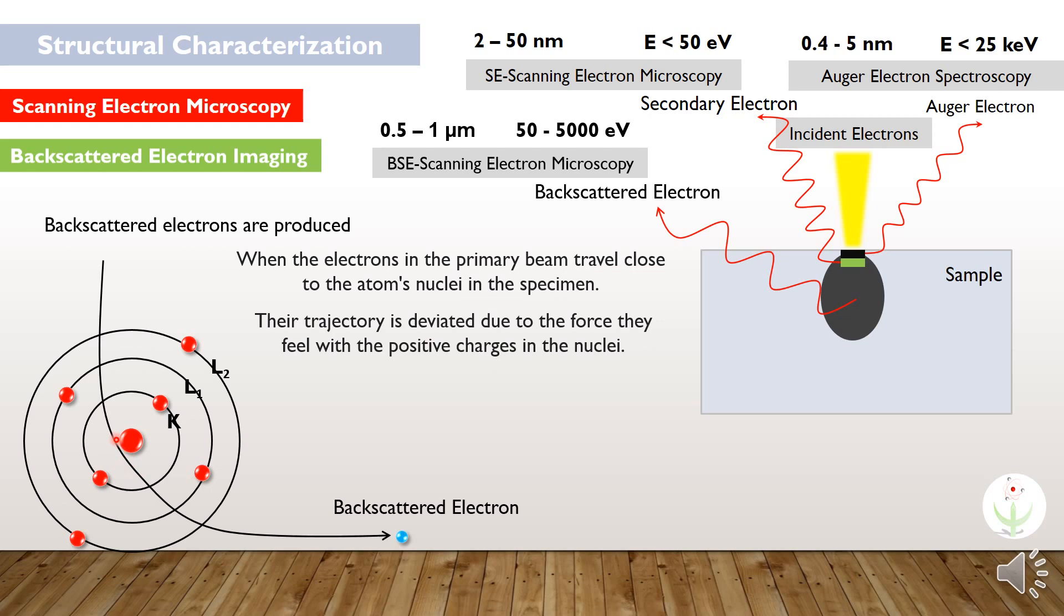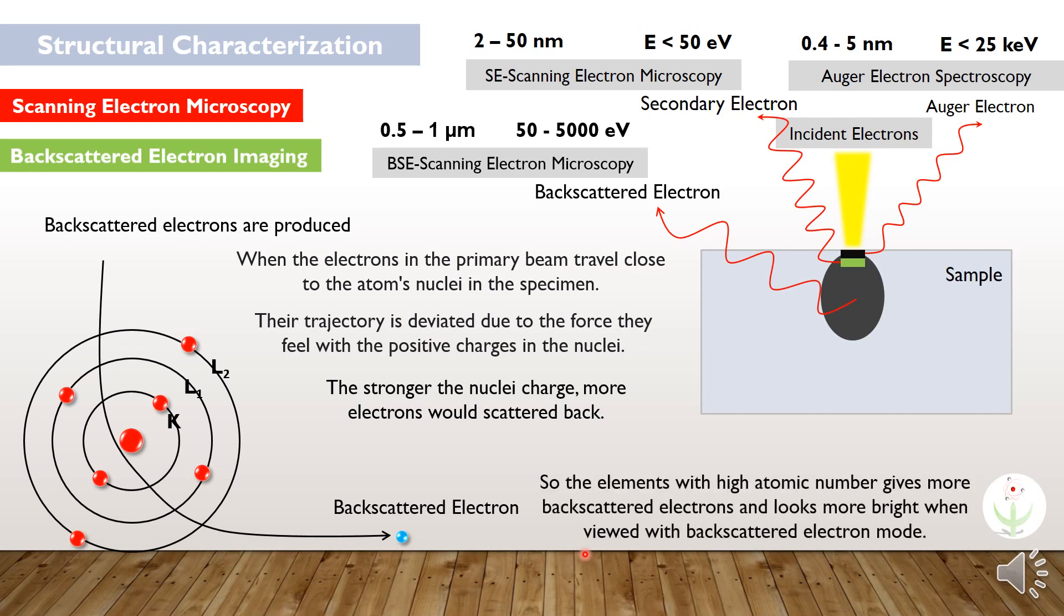These backscattered electrons are produced when the electrons in the primary beam travel close to the atom's nuclei. Their trajectory is deviated due to the force they feel with the positive charge in the nuclei. The stronger the nuclear charge, more electrons will scatter back. That is why elements with a high atomic number give more backscattered electrons and look more bright when viewed with the backscattered electron mode.